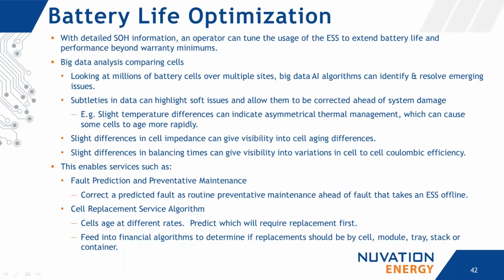We can also run cell replacement service algorithms, paying attention to cells that are aging at different rates to predict which will require replacement first. Then we can look at the cost of a truck roll and the labor required for replacements, and feed that into a financial algorithm to determine whether we should be doing replacements at the cell level, the module level, the tray level, full stacks, or full containers. There are different ways these calculations can be run.